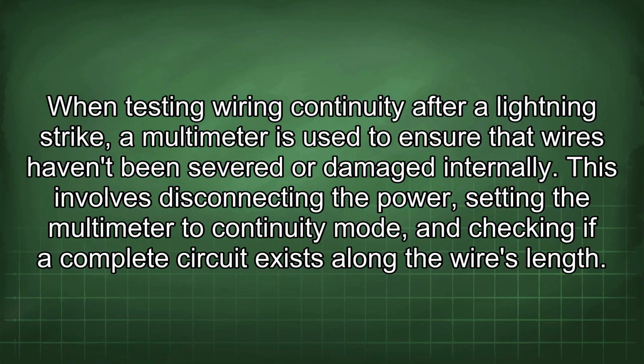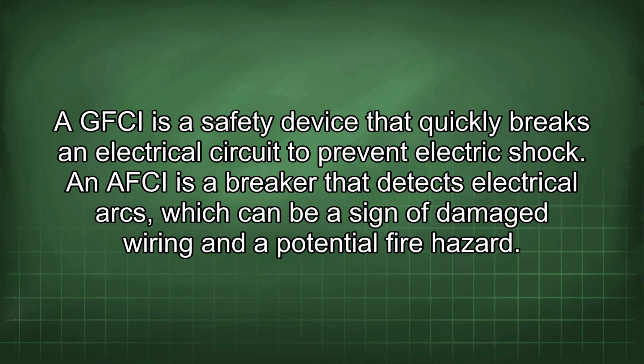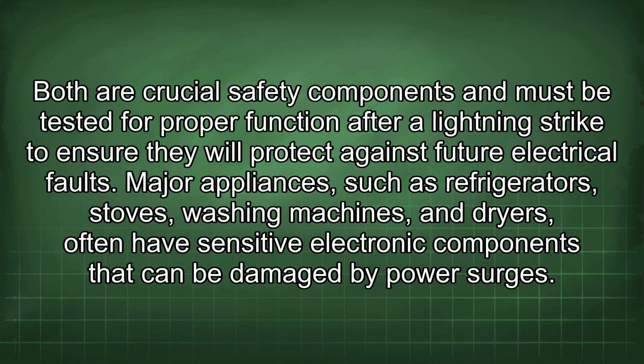A GFCI is a safety device that quickly breaks an electrical circuit to prevent electric shock. An AFCI is a breaker that detects electrical arcs, which can be a sign of damaged wiring and a potential fire hazard. Both are crucial safety components and must be tested for proper function after a lightning strike to ensure they will protect against future electrical faults.